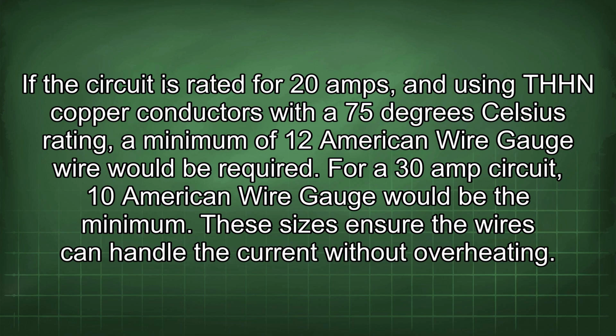If the circuit is rated for 20 amps, and using THHN copper conductors with a 75 degrees Celsius rating, a minimum of 12 American wire gauge wire would be required. For a 30 amp circuit, a 10 American wire gauge would be the minimum. These sizes ensure the wires can handle the current without overheating.